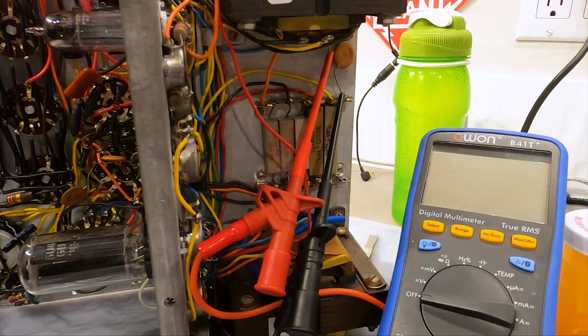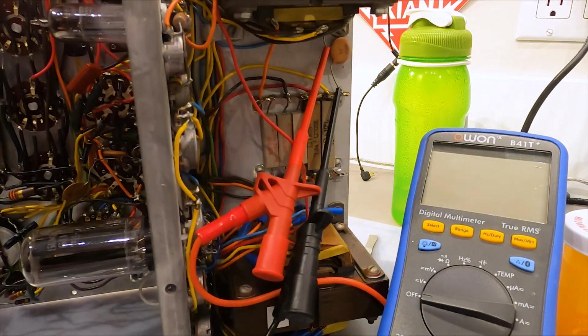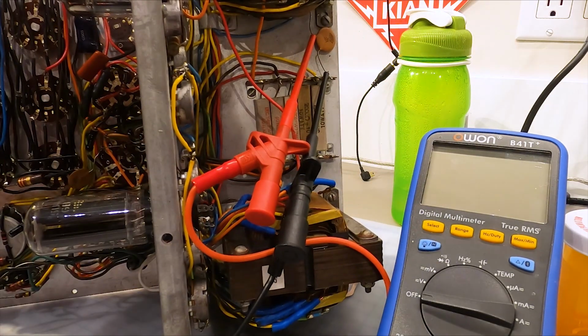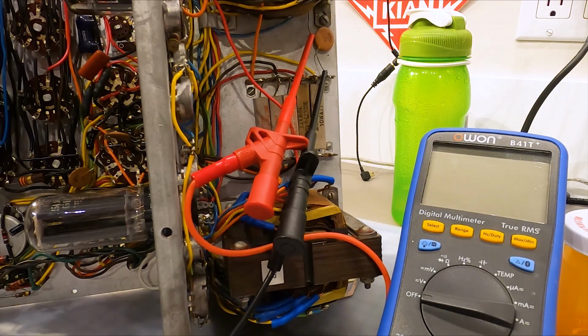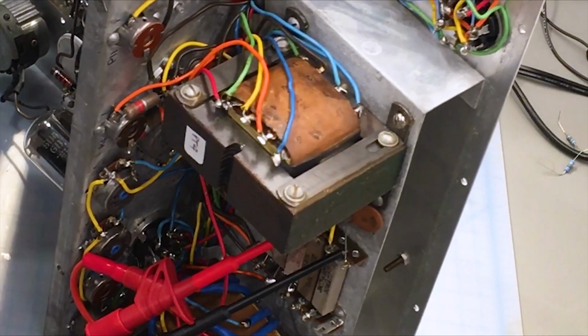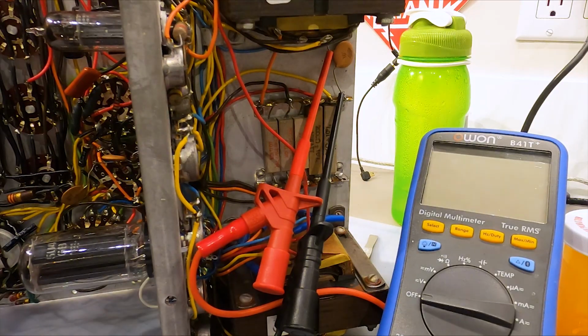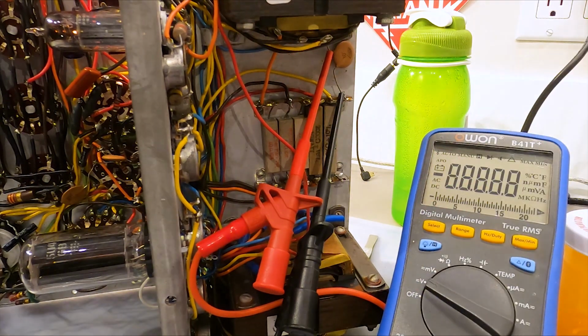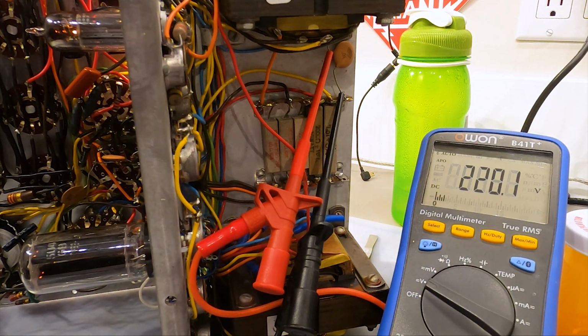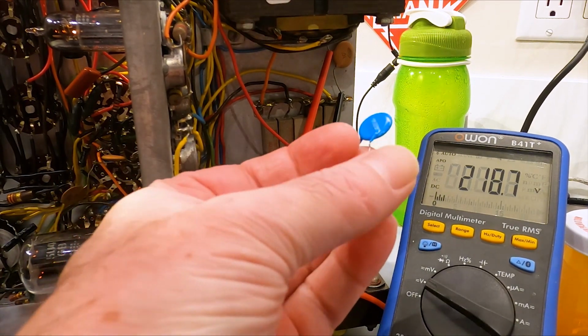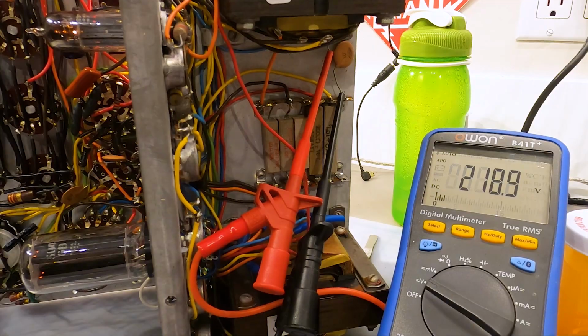So while examining the schematic for any other potential safety issues, it occurred to me that this small capacitor here linked to PT4 is going directly to ground off of the center tap of the secondary from the transformer. And indeed, if we power up the instrument and measure the voltage across this capacitor, we can see that it's on the order of 220 volts DC. It'll probably descend slightly as the rectifiers heat up. So a failure of this capacitor in the form of a short could be a safety hazard. And so what I'd like to do is replace it with a proper X and Y rated safety capacitor. So I'll be doing that momentarily.